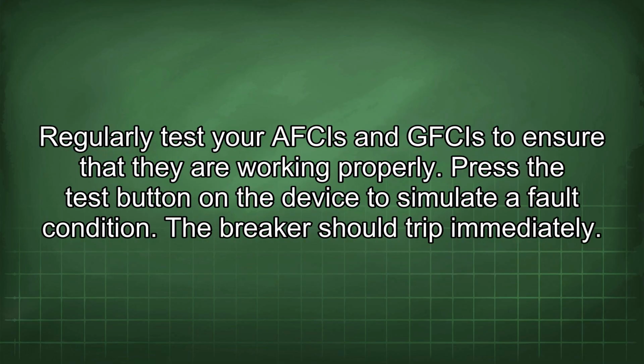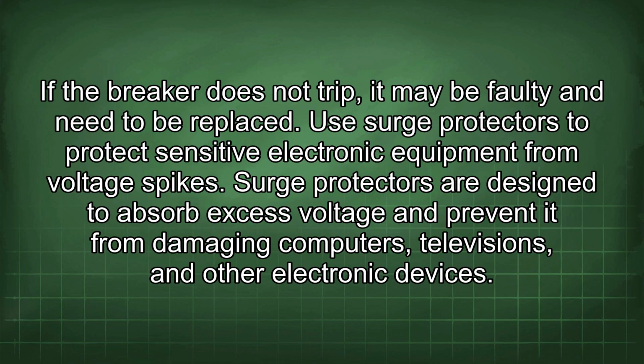Regularly test your AFCIs and GFCIs to ensure that they are working properly. Press the test button on the device to simulate a fault condition. The breaker should trip immediately. If the breaker does not trip, it may be faulty and need to be replaced.